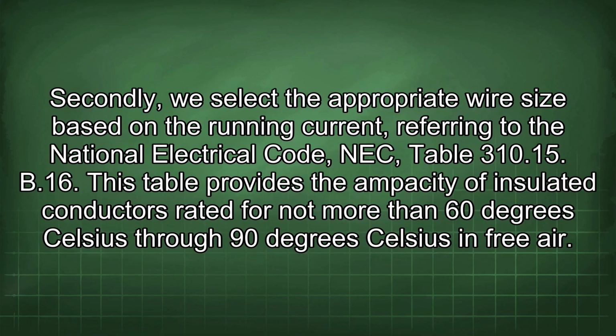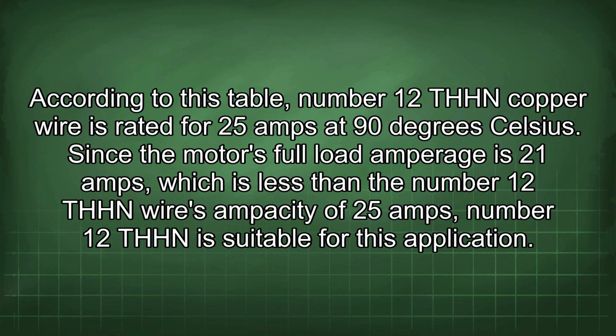Secondly, we select the appropriate wire size based on the running current, referring to the National Electrical Code, NEC, Table 310.15(B)(16). This table provides the ampacity of insulated conductors rated for not more than 60 degrees Celsius through 90 degrees Celsius in free air. According to this table, number 12 THHN copper wire is rated for 25 amps at 90 degrees Celsius. Since the motor's full load amperage is 21 amps, which is less than the number 12 THHN wire's ampacity of 25 amps, number 12 THHN is suitable for this application.